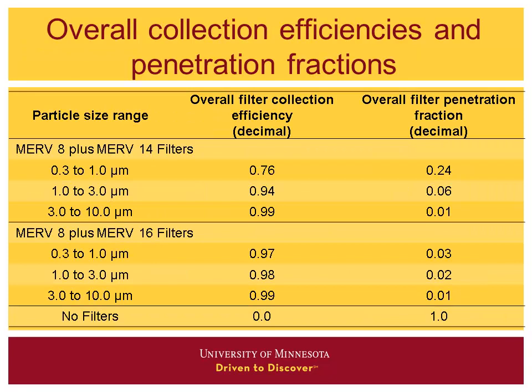Our overall collection efficiencies: MERV 14 collects only about 76% of the very small particles (0.3–1 micron), so 24% passes through. Collection efficiency at 1–3 microns is 0.94, and greater than 3 microns is 0.99. MERV 16 efficiencies are 0.97, 0.98, and 0.99 across those size ranges. We also ran cases without any filters to show that impact.